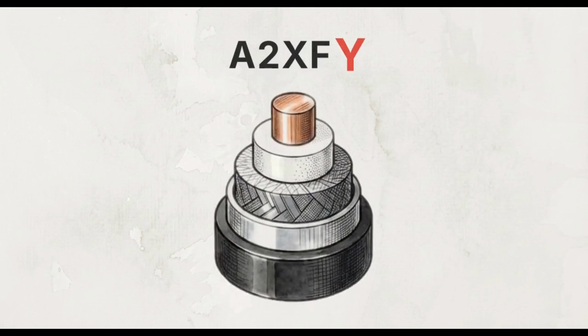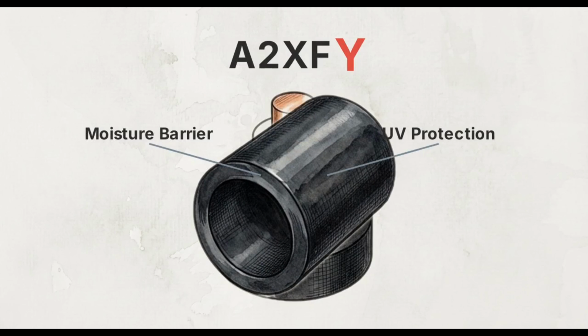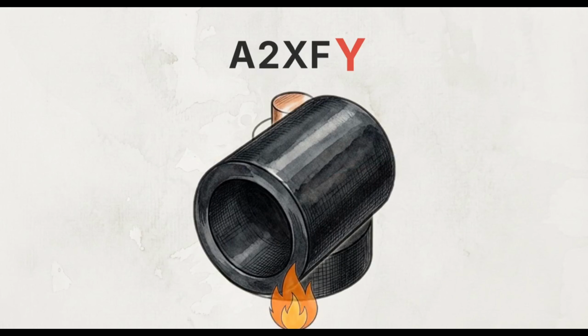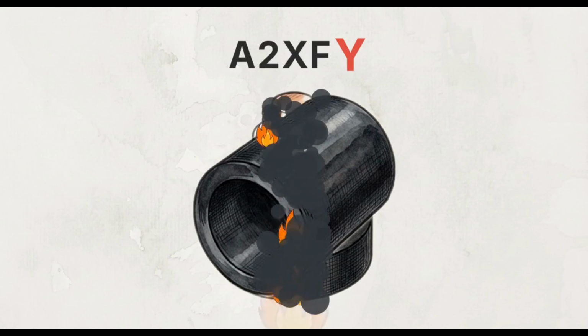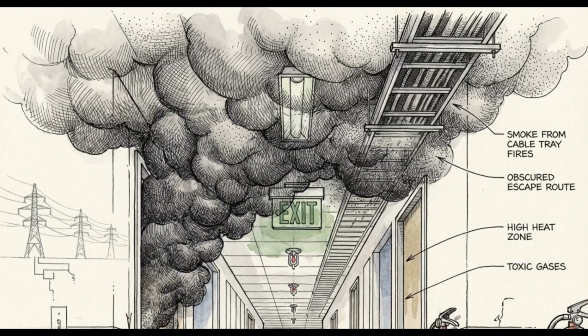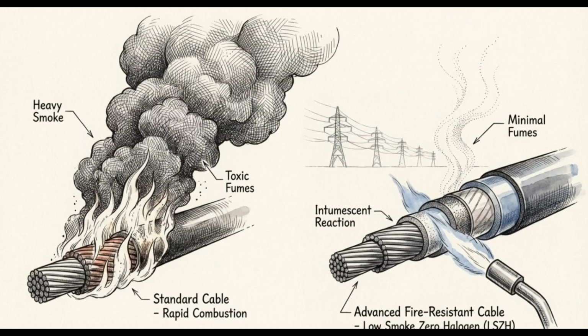The final Y indicates the outer jacket. Traditionally made of PVC, this layer shields the internal components from moisture and UV radiation. However, standard PVC is a highly efficient fuel during a structural fire, rapidly propagating flames vertically. Combustion releases dense, vision-obscuring smoke and toxic halogen acid gas, which are primary hazards during emergency evacuations. Dense urbanization has driven a shift toward low-smoke, zero-halogen compounds, which completely eliminate chlorine and fluorine from the outer jacket's chemical composition.